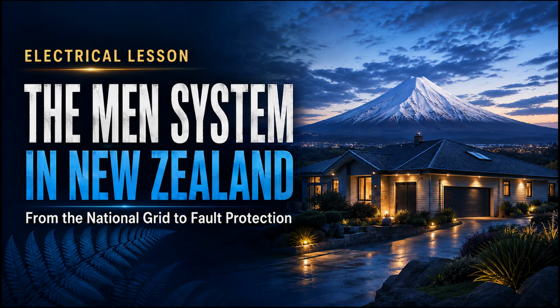At grid substations, electricity is delivered to local distribution companies, sometimes called lines companies. The voltage is stepped down for regional and local distribution. The exact voltage sequence depends on the network, but 33 kV and 11 kV are common distribution levels. Closer to customers, a local distribution transformer steps the voltage down again. Its low-voltage secondary normally supplies 4 conductors: 3 line conductors, L1, L2 and L3, and a neutral conductor.